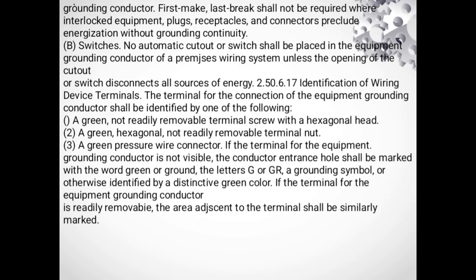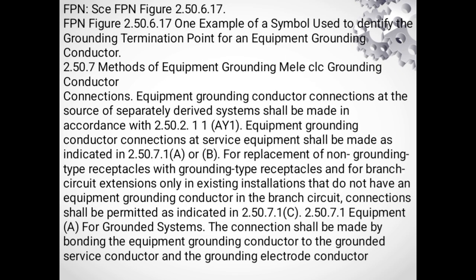2.50.6.17 Identification of wiring device terminal. The terminal for connection of the equipment grounding conductor shall be identified by one of the following. A. A green, not readily removed terminal screw with a hexagonal head. B. A green, hexagonal, not readily removed terminal nut. C. A green pressure wire connector. If the terminal for the equipment grounding conductor is not visible, the conductor entrance hole shall be marked with the word green or ground, the letter G or GR, a grounding symbol, or otherwise identified by a distinctive green color. If the terminal for the equipment grounding conductor is readily removable, the area adjacent to the terminal shall be similarly marked. Figure 2.50.6.17: one example of the symbol used to identify the grounding termination point for an equipment grounding conductor.